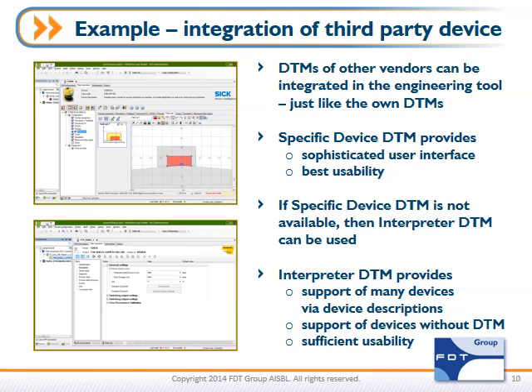Similarly, we can integrate third-party devices into this engineering tool. DTMs from other vendors integrate in the same manner as DTMs from the main supplier. That specific device DTM provides the same sophisticated user interface and best usability for that particular device. If a specific device DTM is not available, it may be possible to use an interpreter DTM. These interpreter DTMs support many devices via their device description. They don't have a special purpose-built DTM, but they provide sufficient functionality to configure the device — without the same rich graphical interface and diagnostics of a full-featured DTM — while still allowing the device to integrate into the engineering tool in the same manner.